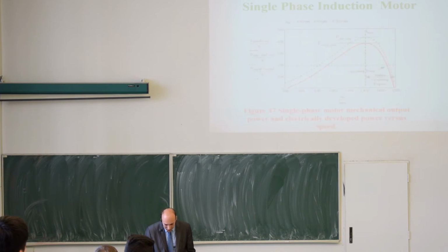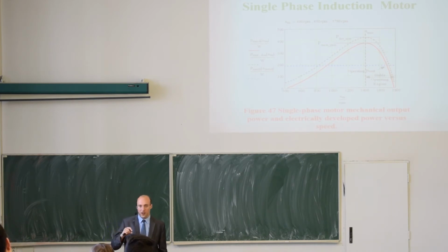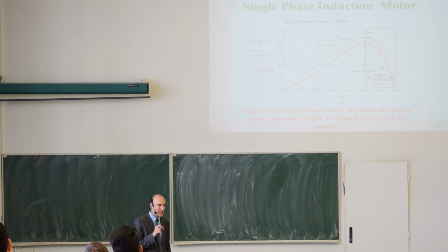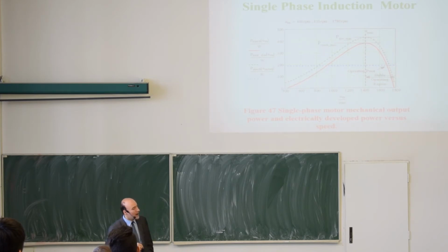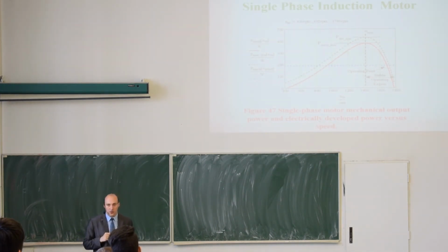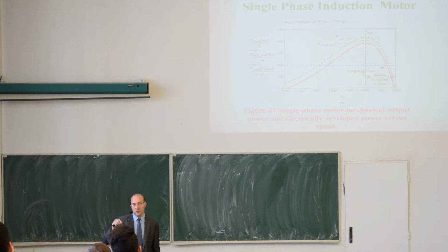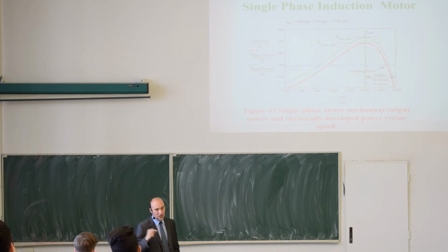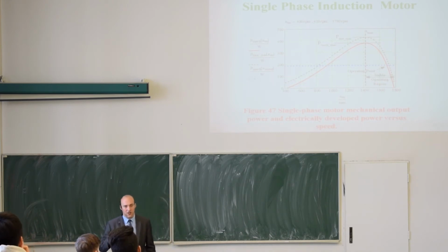So what will be the impact on the torque speed characteristic of the single phase induction motor? If you power it directly from the power network without any external capacitors, you will find out that the torque speed characteristic looks like this. And it looks similar at first to the three-phase motor. But here at zero speed, if you would go further here, you would find out that it has zero torque. So without an external capacitor, without any external winding that is being powered by a second power supply with a different phase shift, the starting torque of the single phase induction motor is zero.